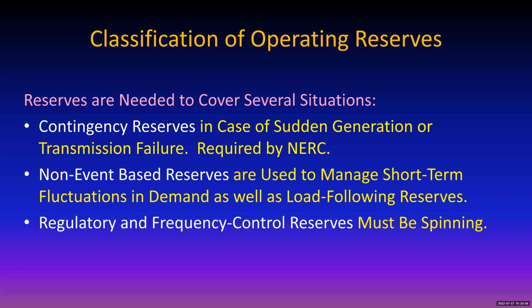Anything that's there for frequency controlling regulation has to be spinning right away. There's simply not time to get them up to speed if it's a rotating reserve. The other thing that will undoubtedly happen with flywheels, maybe it already has, is they'll be dumping their output into big inverters as well. As they slow down, they can still contribute, though it's a little less efficient that way because you have to convert to DC and then back to AC. But you can run them a little bit longer and still maintain very constant frequency.